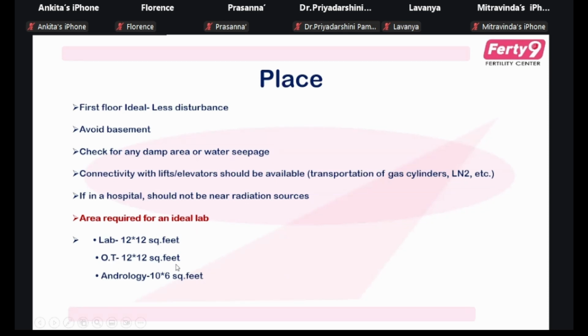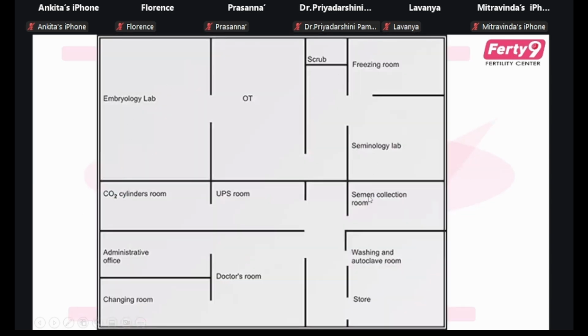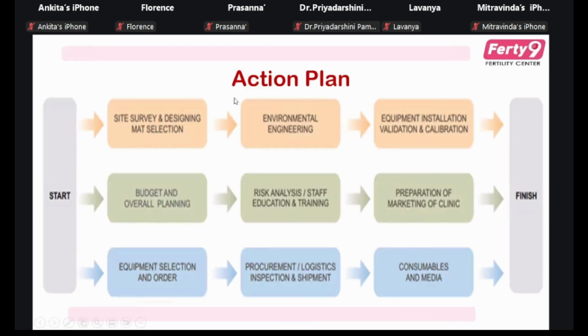OT is again 12 by 12 square feet, andrology 10 by 6 square feet is enough. This is the shape of an embryology lab and system. Embryology lab and OT should be interconnected, with a scrub area, and the freezing room should also be near the embryology lab. We have to have separate rooms for freezing, semen collection, andrology, and the doctor's room. Even the carbon dioxide cylinder room should be separate, and we have to make sure carbon dioxide is adequately filled for the ART lab.